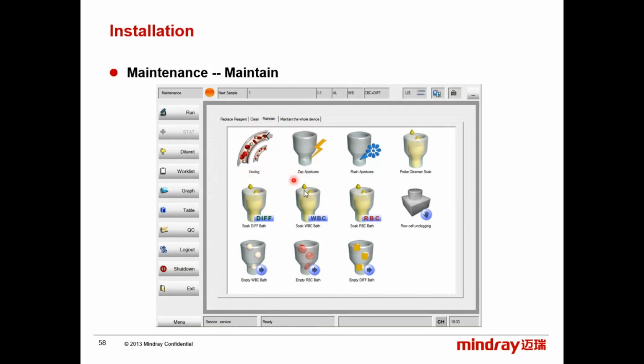This will apply high AC voltage to burn all the remaining membranes of the cells on the electrodes. Why do we need this one? Maybe you will see some increase in the MCV or in the MPV. This is an indicator of this phenomenon. It means that initially you have some impedance caused by those membranes. So when you get the mean size of the cells, you will get the size of the cells plus the impedance of the membranes stuck to the electrodes. So here you will get some increase, some right shift in the histograms.